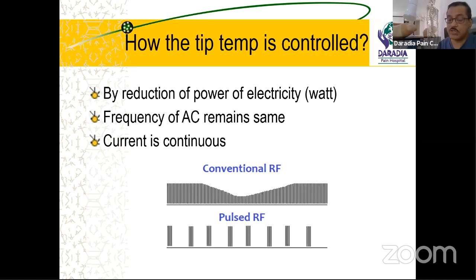Why 42 degrees? Because it has been seen that in our body, there are different kinds of tissues having different heat labile temperatures. But below 45 degrees, no tissues are damaged with the heat. So we are keeping it at 42 so that there will be no damage of any structures by heat. So pulse radio frequency is one way. It's very safe that we are not going to damage any tissues with heat. So pulse radio frequency is safer, but pulse radio frequency has failures as well.